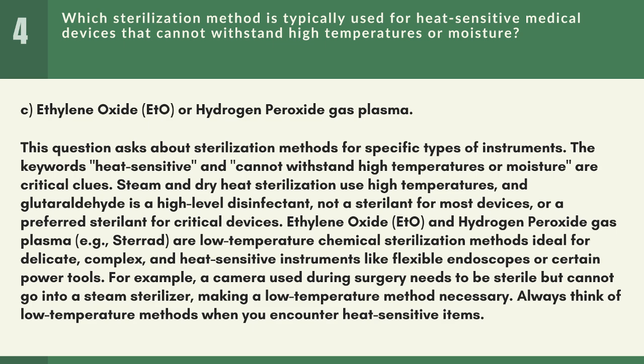This question asks about sterilization methods for specific types of instruments. The keywords heat-sensitive and cannot withstand high temperatures or moisture are critical clues. Steam and dry heat sterilization use high temperatures, and glutaraldehyde is a high-level disinfectant, not a sterilant for most devices, or a preferred sterilant for critical devices. Ethylene oxide, EtO, and hydrogen peroxide gas plasma, e.g., Sterrad, are low-temperature chemical sterilization methods ideal for delicate, complex, and heat-sensitive instruments like flexible endoscopes or certain power tools. For example, a camera used during surgery needs to be sterile but cannot go into a steam sterilizer, making a low-temperature method necessary. Always think of low-temperature methods when you encounter heat-sensitive items.